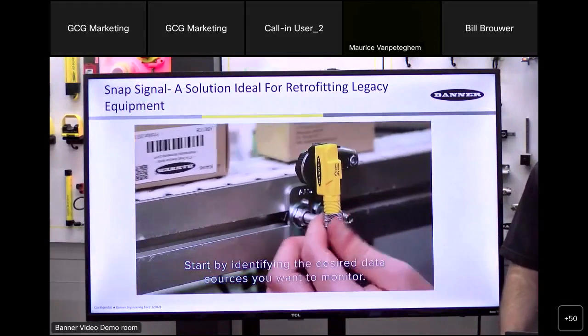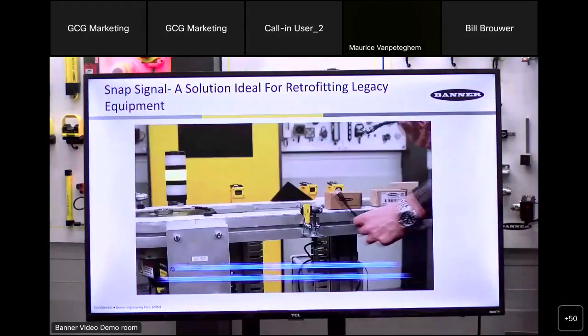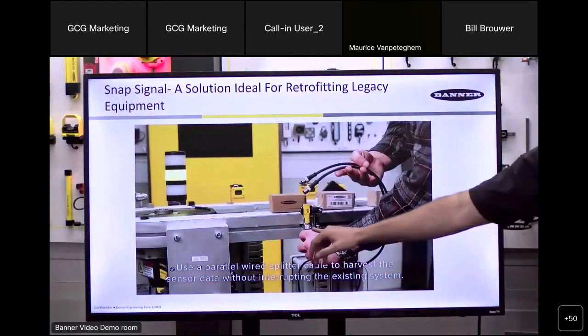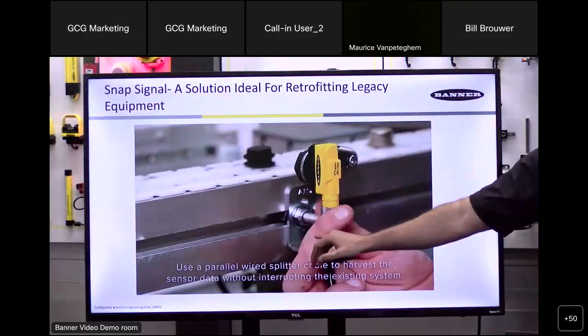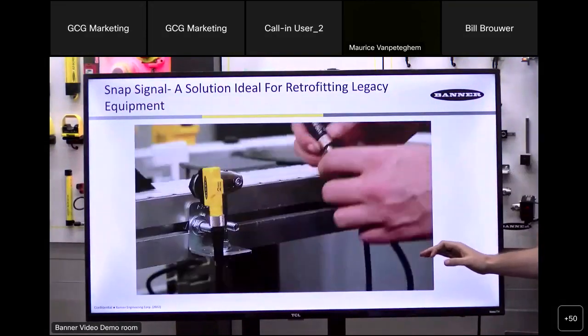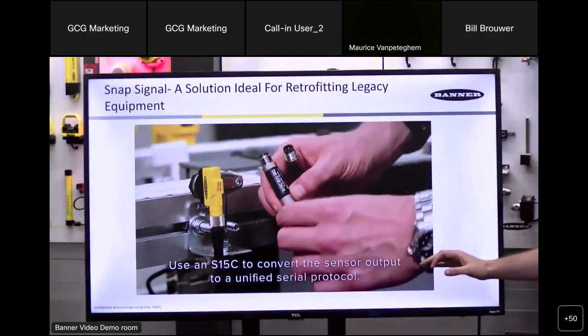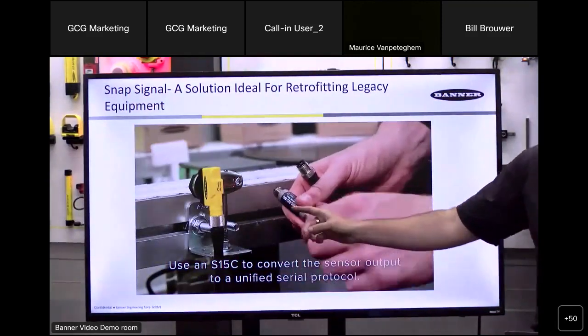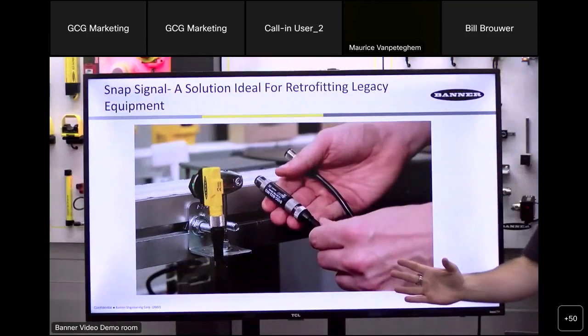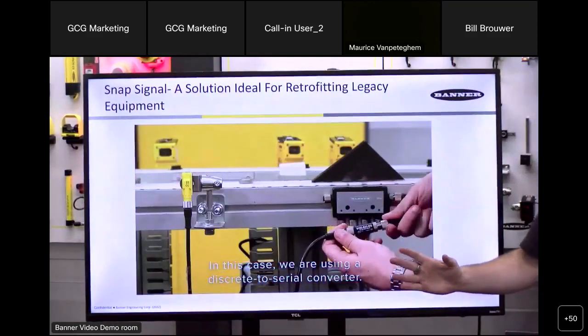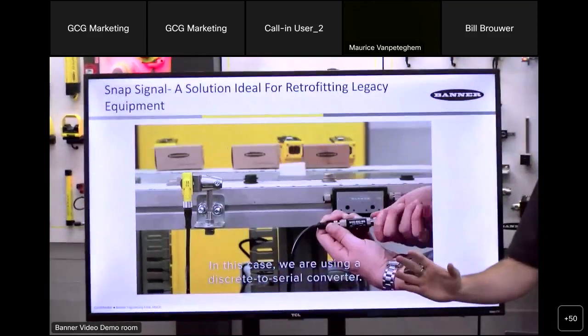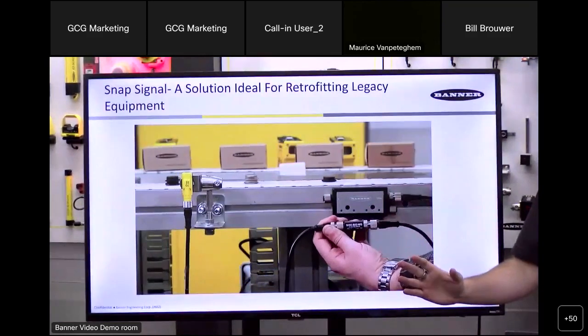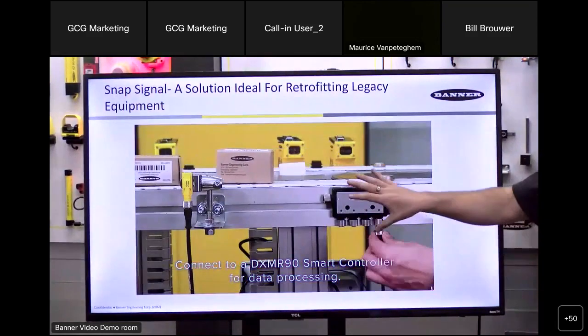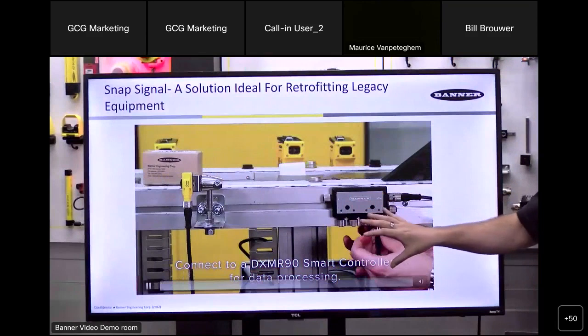With Snap Signal, you could use something as simple as a parallel wired splitter to plug in the sensor, with one branch going into the converter and one branch going into your existing control system. So it's running completely in parallel to the existing control system. The existing PLC isn't seeing this overlay at all.